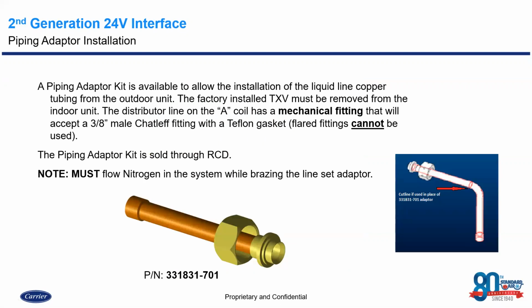This is going to be our male Chatleff fitting that we need not only on the FB and FXs, but also with our gas furnace combinations, because they are traditional residential units which have TXV in that indoor unit or in the coil, in the case coil, depending on what your pairing is. So we need to make sure that we have this male Chatleff fitting to remove that TXV from the system, and then of course hook up the actual Chatleff fitting itself to the distributor feeding into the indoor coil. If we do not, we're going to end up with a double pressure drop, and of course, as we all know, that system isn't going to work at all.